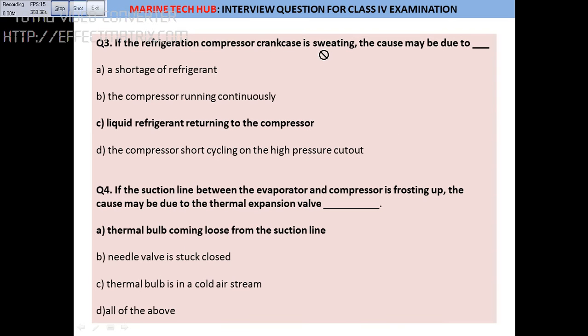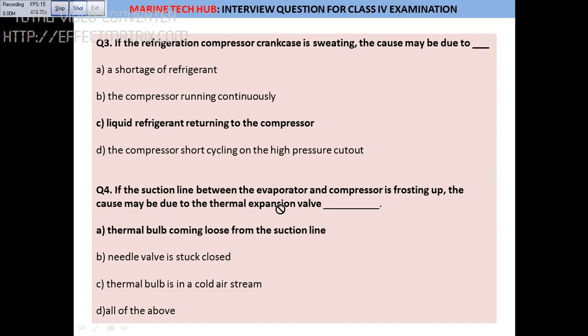Question 3: If there is sweating in the crankcase of the compressor — when you touch the compressor and see a lot of sweating — that means liquid refrigerant is returning to the compressor. Only gas should enter the compressor; if liquid is coming in, that is not good and will cause sweating. Make sure the expansion valve is working correctly and the bulb position is not loose.